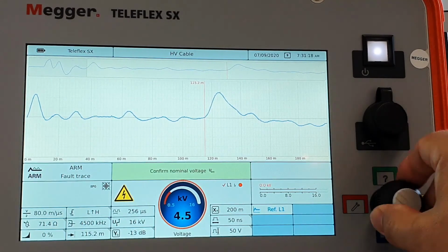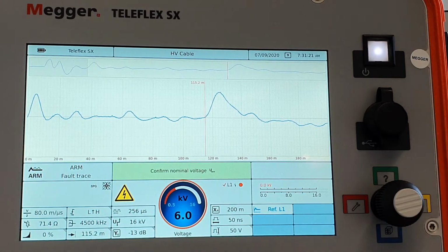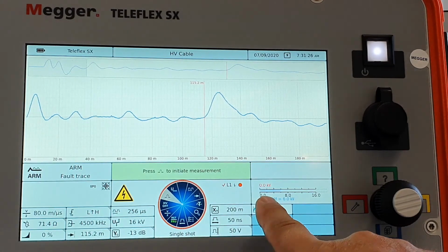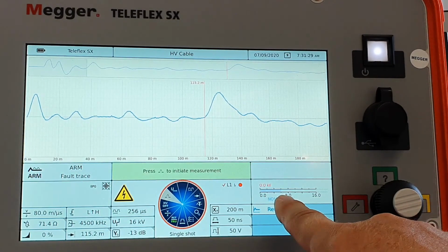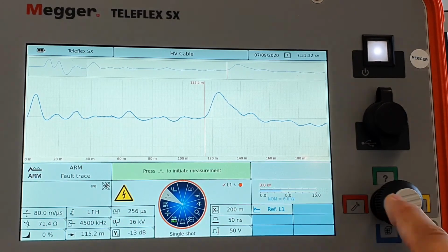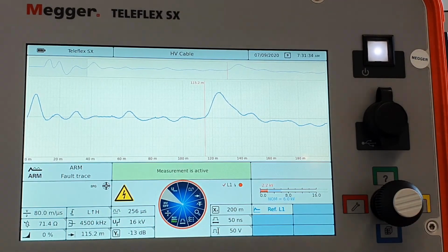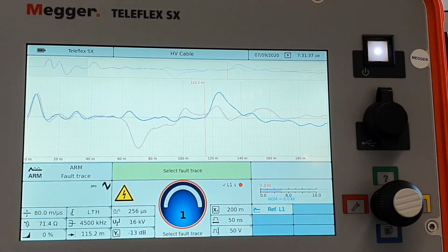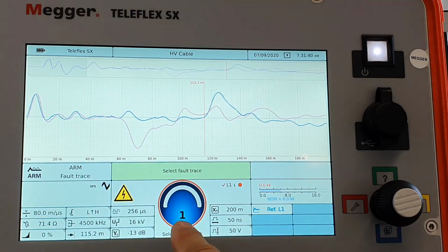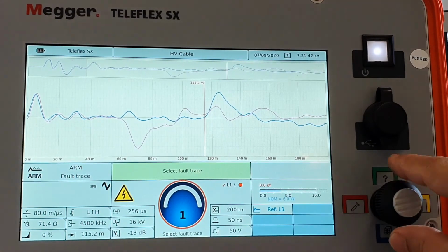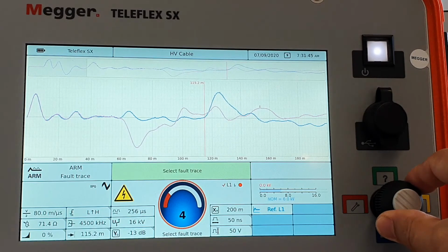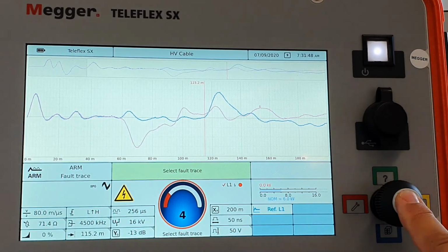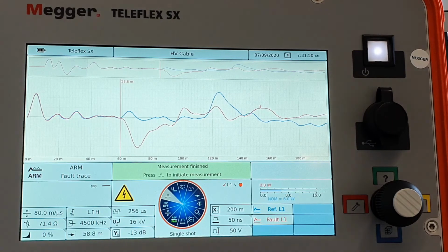Now I give it a certain voltage that I need, a bit higher than my breakdown. I see here my range is 16 kV. I have set it to 6 kV. Start. My voltage is now applied, flashing over, and now I see trace 1 out of 15. I can select the nicest one and confirm. And my cursor jumps right to the fault position at 58.8 meters.